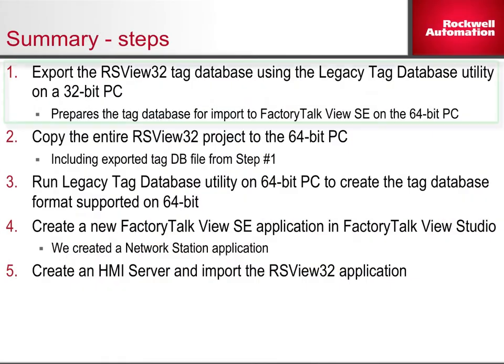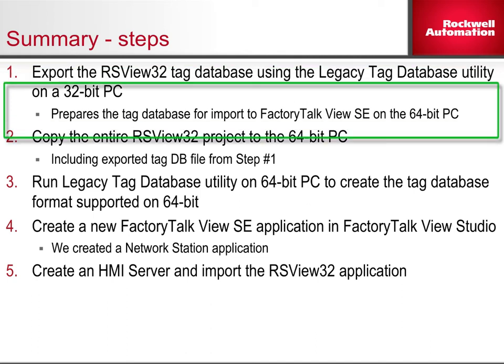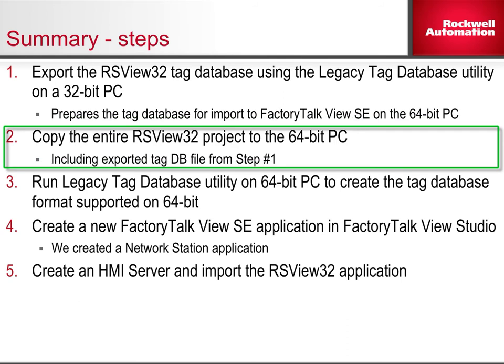Step 1: Export the RSView32 tag database using the Legacy Tag Database utility on a 32-bit PC. This prepares the tag database for import to FactoryTalk View SE on the 64-bit PC. Step 2: Copy the entire RSView32 project to the 64-bit PC, including the exported tag DB file from step 1.